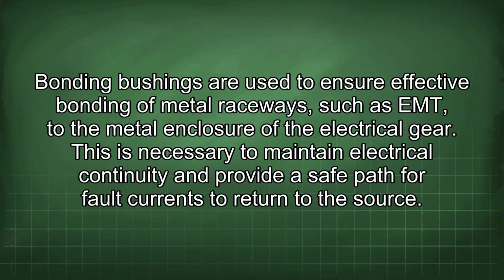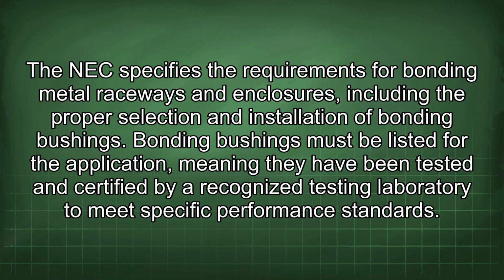Bonding bushings are used to ensure effective bonding of metal raceways, such as EMT, to the metal enclosure of the electrical gear. This is necessary to maintain electrical continuity and provide a safe path for fault currents to return to the source. The NEC specifies the requirements for bonding metal raceways and enclosures, including the proper selection and installation of bonding bushings. Bonding bushings must be listed for the application, meaning they have been tested and certified by a recognized testing laboratory to meet specific performance standards.